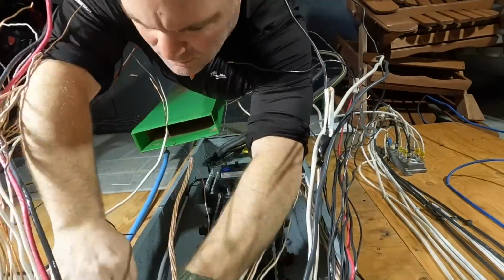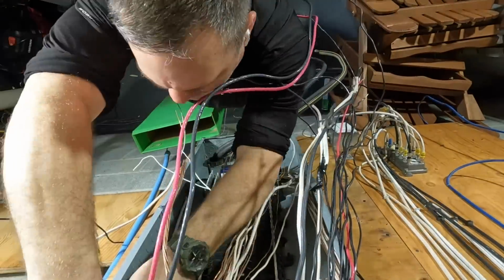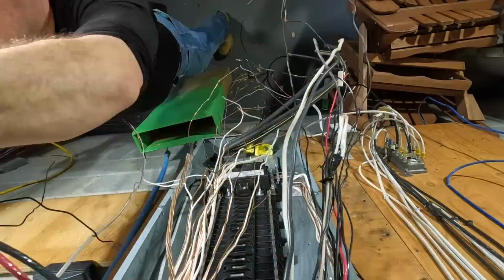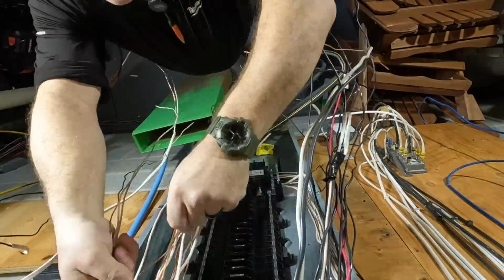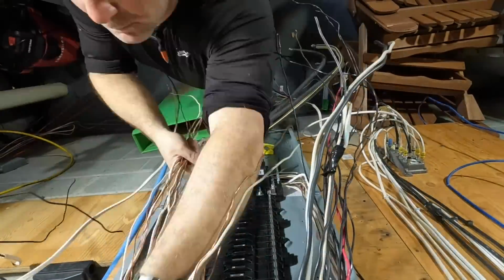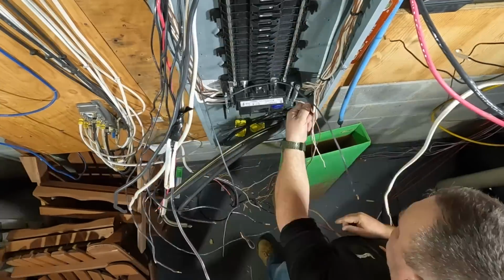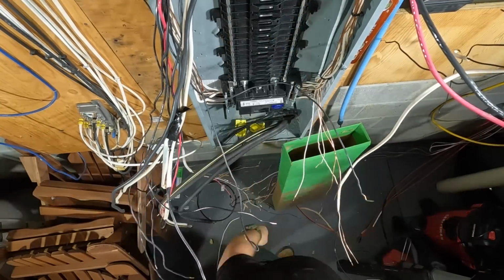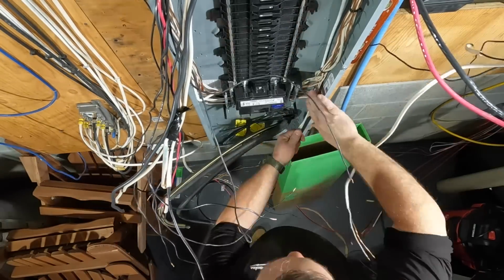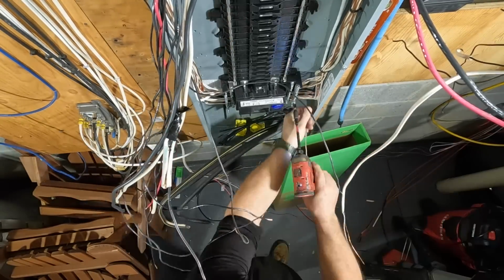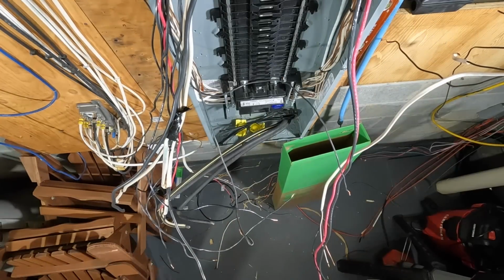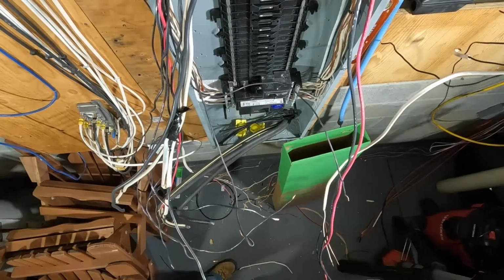Electrical equipment and wiring and other electrically conductive material likely to become energized shall be installed in a manner that creates a low impedance circuit facilitating the operation of the overcurrent device or ground detector for high impedance grounded systems. It shall be capable of safely carrying the maximum ground fault current likely to be imposed on it from any point on the wiring system where a ground fault may occur to the electrical supply source. The earth shall not be considered an effective ground fault current path.